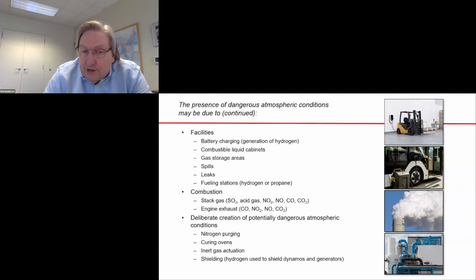Stack gas, SO2, acid gas, oxides of nitrogen like nitric oxide and nitrogen dioxide, carbon monoxide, carbon dioxide. These are all dangerous contaminants, and frequently you need to install protective measures to keep track of concentration or to keep a buildup from occurring. You have engine exhaust. Similarly, you have CO, NO2, NO, CO2 in the exhaust that could be a concern. Sometimes you're deliberately creating dangerous atmospheric conditions during the manufacturing process. The manufacturing process might include nitrogen purging, use of curing ovens under a nitrogen purge, inert gas actuation. That's something you see repeatedly or very commonly at steel mills, aluminum mills, and foundries.